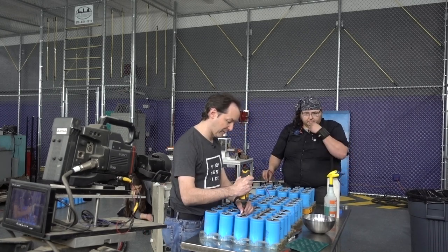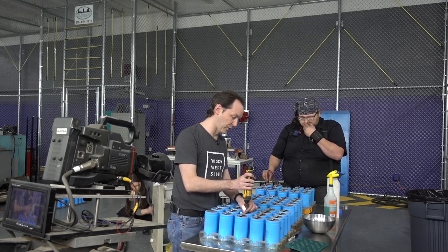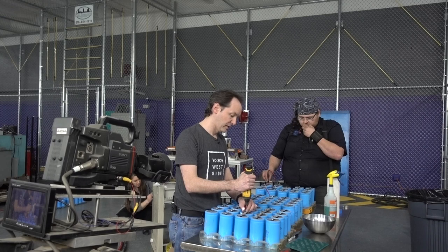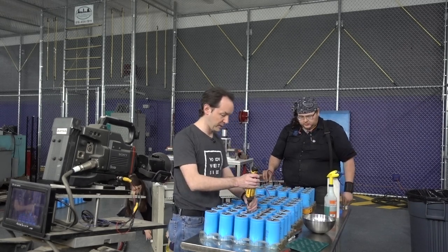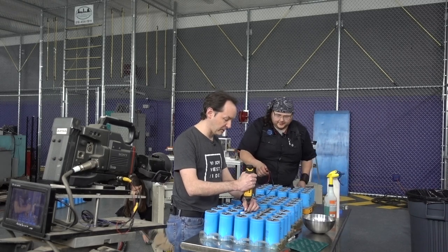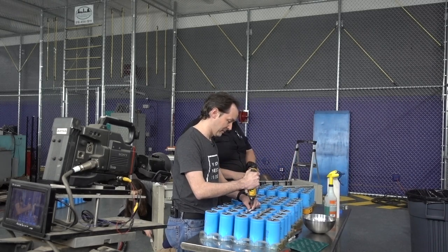Those are vents. If a cap fails in normal use, not pulse use, but normal use, the little vent can pop out and it keeps the can from grenading. Faults in here happen so fast that that doesn't have time. It's literally the repositioning.